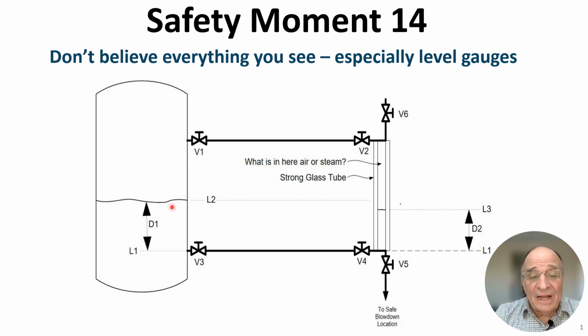This fluid may be in a very hot vessel. This is a long tube, and this fluid is in a cold vessel. So being cold, this fluid is more dense than this fluid. And even though it's the same exact fluid, let's say it's water, this could be a boiler, and you're reading the boiler temperature, and this could be colder water on the outside. Now, this boiler, if it has bubbles of air in it, it may be less dense than this liquid level. This liquid level might show up here. So you're not reading the actual level.